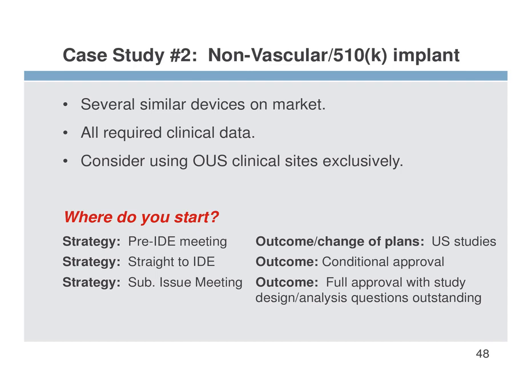But then we looked at the conditional approval questions, and not only did we get some unreasonable requests to change, I think it was the follow-up intervals, but we also got some of those additional questions you now get with FDA where they say, well, we can approve your IDE study because of all the safety issues, but we're not convinced that it's going to be good enough to actually get you a 510K. And so we said, that sounds like a submission issue meeting. It's time to meet them face to face.